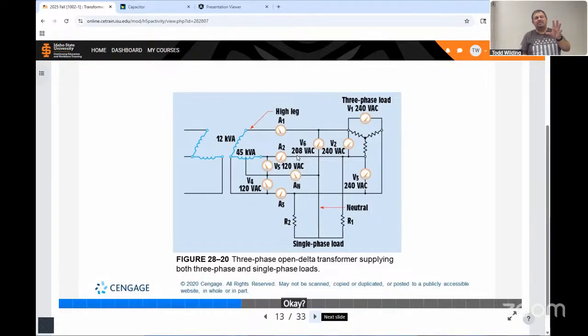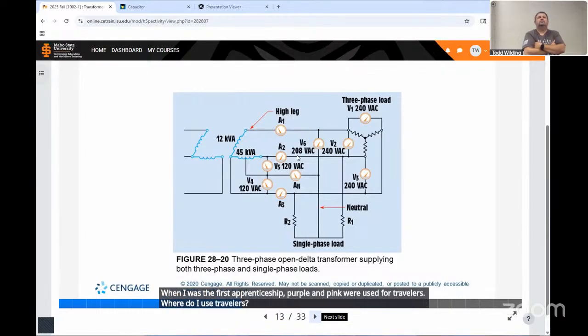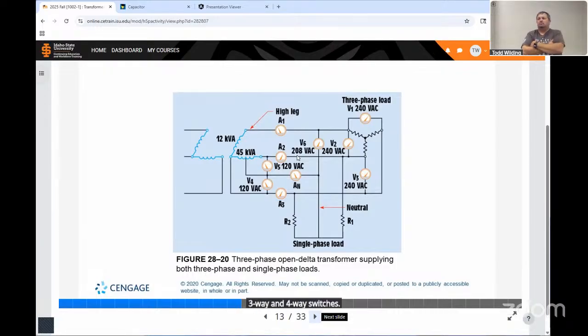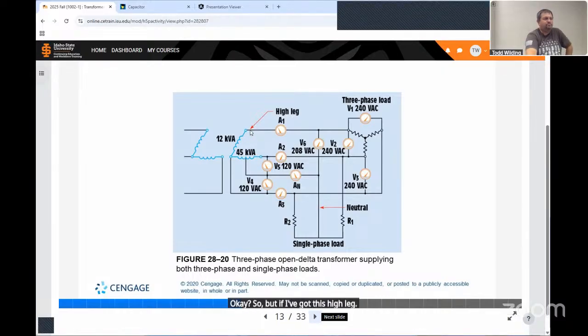There have been a few instances where certain localities, municipalities, cities, contractors, if it's a 480 277, will remove the orange and put purple there. Does not matter. When I was in my first apprenticeship, purple and pink were used for travelers. Where do I use travelers? 3-way and 4-way switches. That is not code, it's not law, it's just a color that we have. But typically a 480 277 is brown, orange, yellow with a gray neutral. But if I've got this high leg, 208 volt, that must be orange.